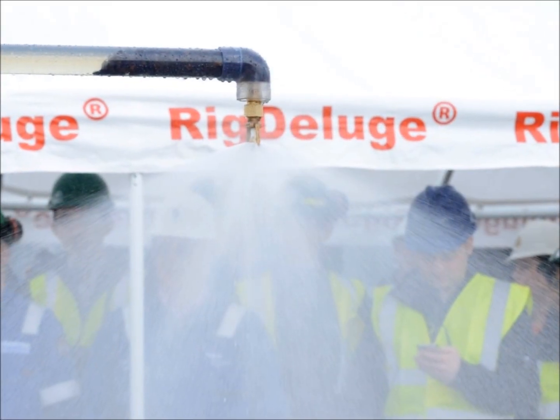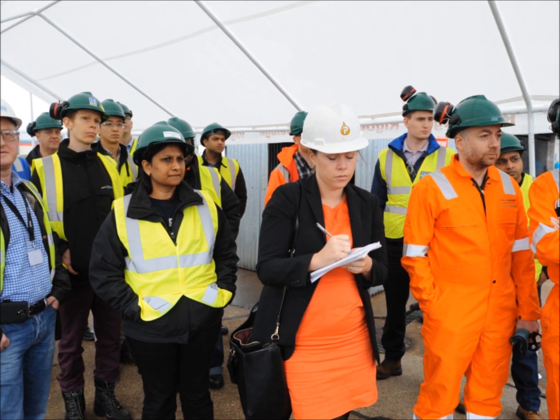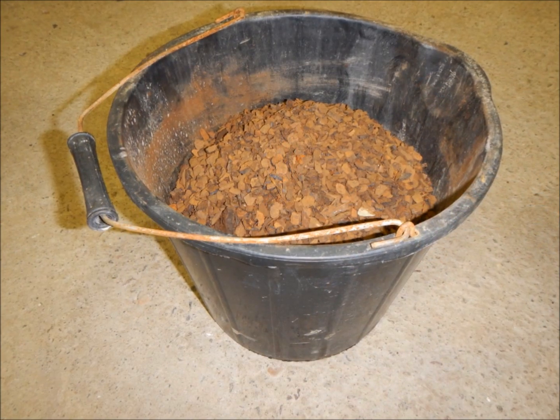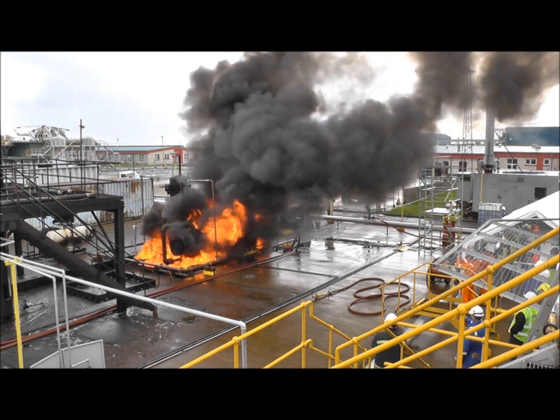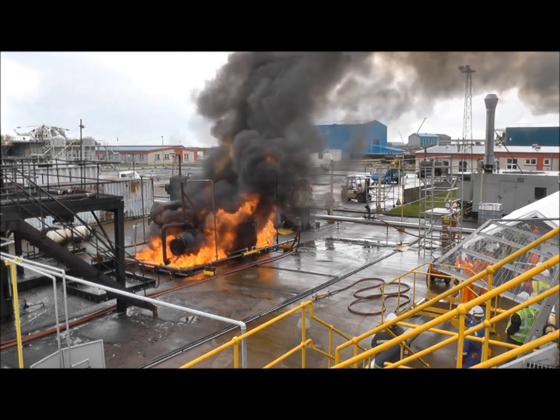RigDeluge recently carried out a demonstration in front of all independent certifying authorities and a multitude of operators and industry experts. We introduced 10 kilograms of debris into a 10-nozzle system delivery line. We then ignited several pool fires and two jet fires. The results show that there were no nozzle blockages and that the fires were contained.